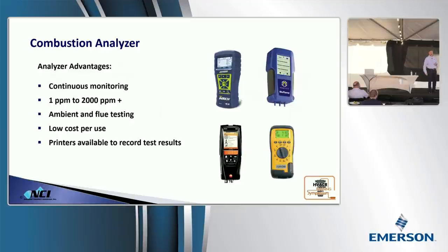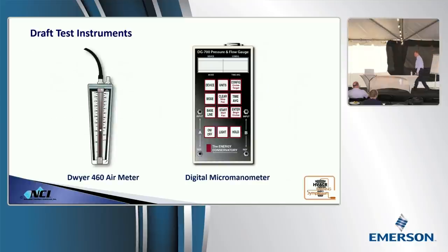You also need draft, not from the combustion analyzer, because if you're measuring it on a natural draft piece of equipment, draft is taken in a different location than your test measurements for combustion. So you've got to make sure you're testing in the right spot. You also need a draft gauge. Oddly enough, this thing's called a Dwyer 460 air meter. It's like $40. You can probably get one from Bill. It really sucks at measuring air, but it's awesome at measuring draft.